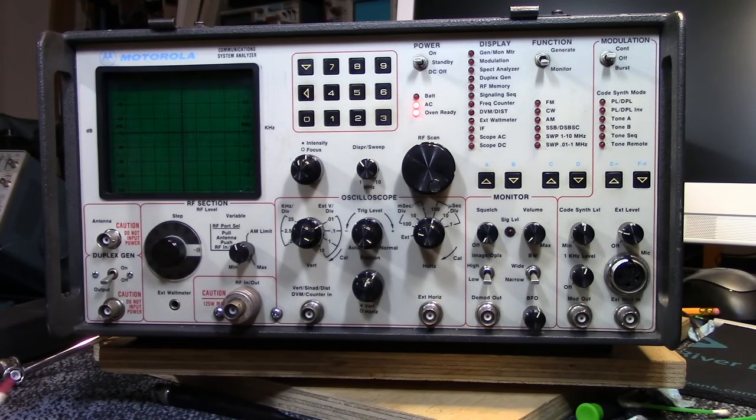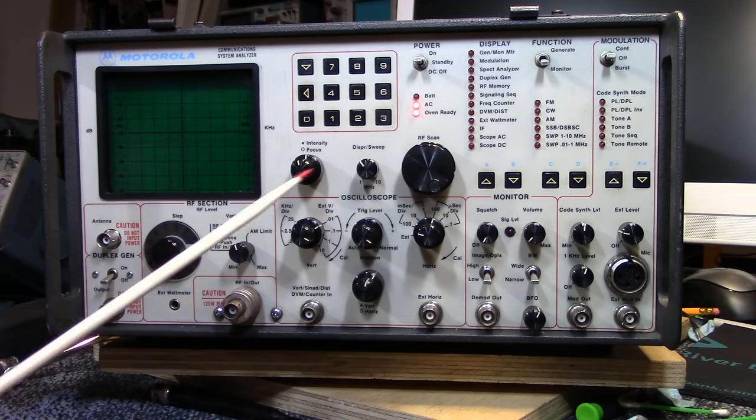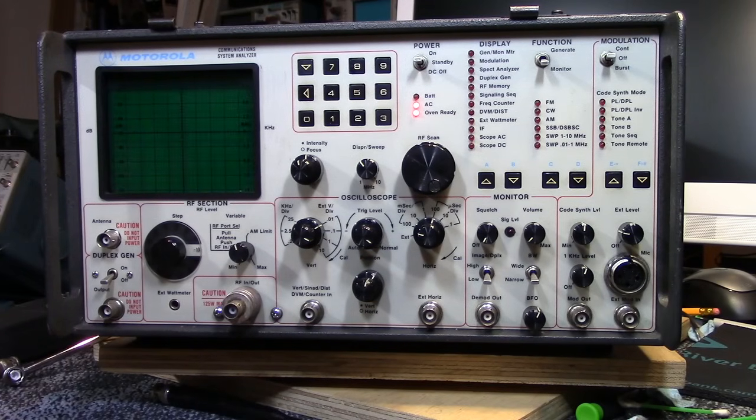It has a sweep generator that'll sweep from 10 kilohertz to 10 megahertz. Has an input sensitivity of 1.5 microvolts for 10 dB SINAD, so it's pretty sensitive. And I'll do some on-air checks on here that'll kind of demonstrate that. For deviation measurement on FM, it has 3 different ranges here of 1, 10, and 100 kilohertz. And the spectrum analyzer section on here will measure from 100 kilohertz per division to 1 megahertz per division, and it'll do that over a range of 1 megahertz to 1 gigahertz.